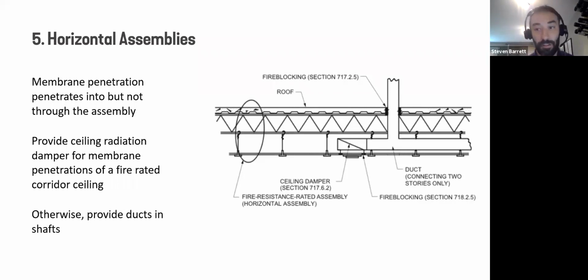You need all of it to get your fire rating. It's not just the roof itself. It's not just the ceiling itself that gives you the fire rating. So in this case, that duct is penetrating just the one portion of the ceiling there at the bottom. So code permits a ceiling radiation damper to be provided. In other cases, if you have a membrane penetration, the duct must be run in a shaft.